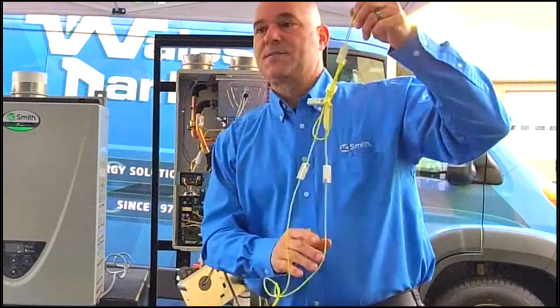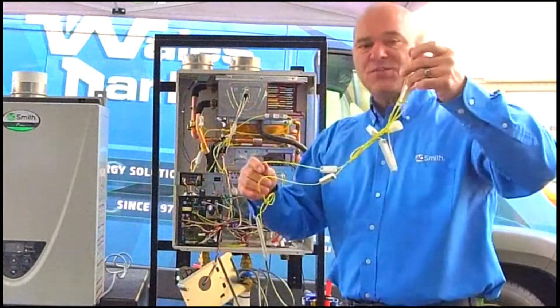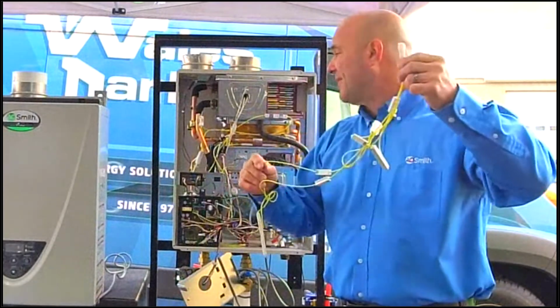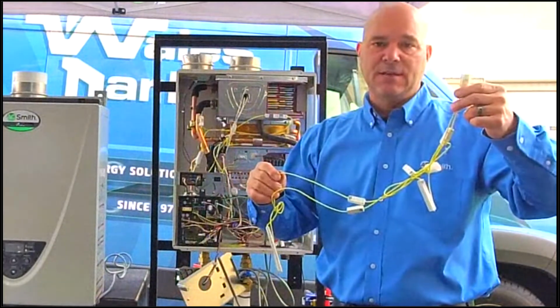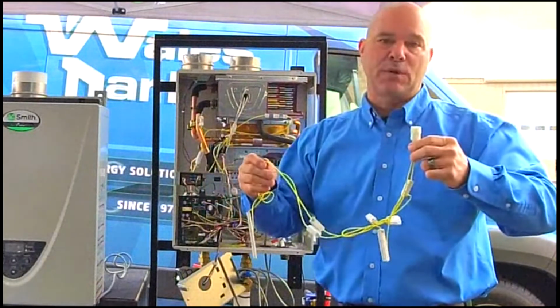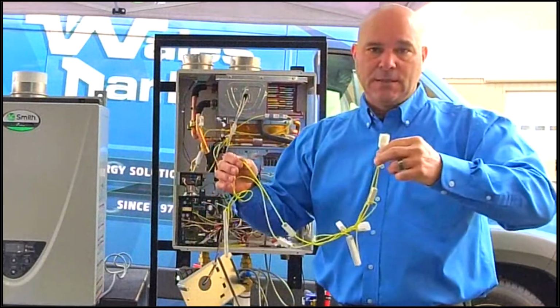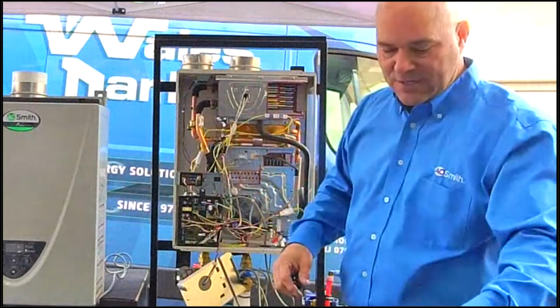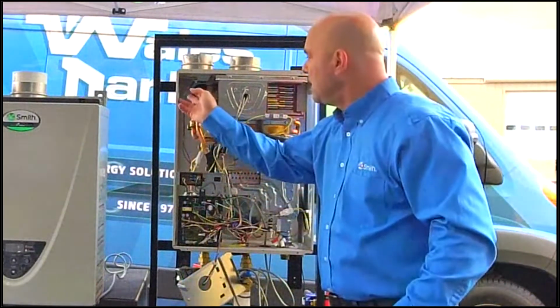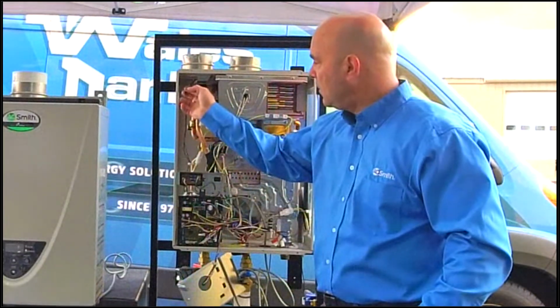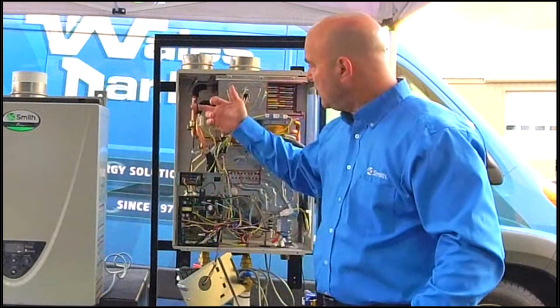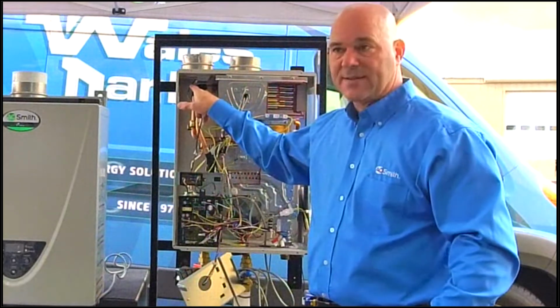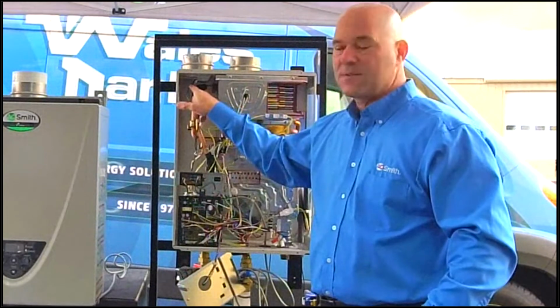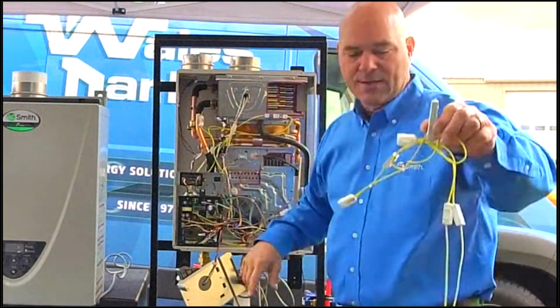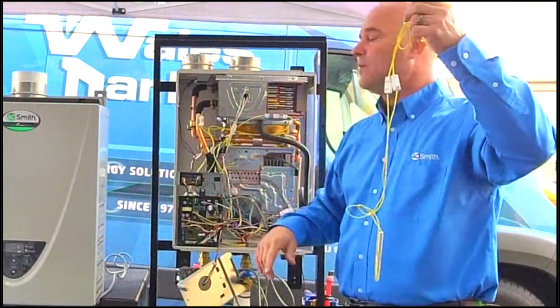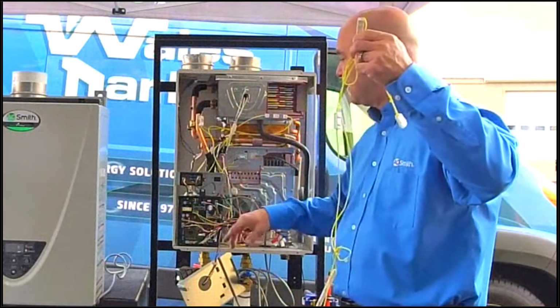All of these yellow wires will come on at 36.5 degrees, and they will shut back off again at 46.4 degrees. What tells these yellow wires to come on? There's a sensor right here on the cold air inlet. This little black wire right here goes up to this black sensor. That is what tells the yellow wires to activate, and they will activate at that 36.5 degrees.